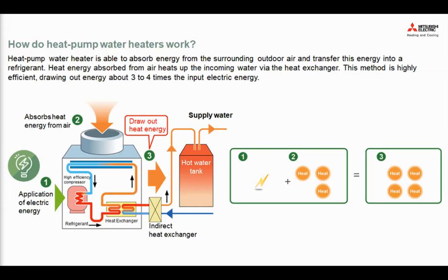I had somebody ask, what does COP stand for, and how is the water kept from freezing in the wintertime? So COP stands for coefficient of performance. So basically how much heating output versus what's the kilowatt input in terms of electricity. So let's say 1 kilowatt of power consumption to generate 4 kilowatts of heat, that will give you a COP of 4. Okay. I have another question. What are the approximate lead times? Oh, I already did that one. Sorry. What type of refrigerant pressure are we looking at here?